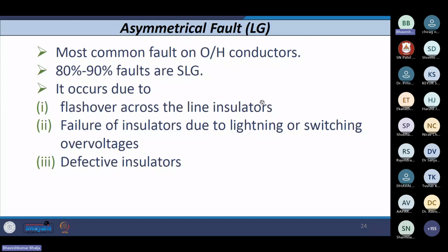Now, why do we bother about spacing between the conductors and the ground clearance? Because these two factors are important when we consider any type of fault. Usually 90 to 95% of faults are asymmetrical in nature, and 90% of those are single line to ground, so we are more concerned about single line to ground. This fault occurs because of flashover across the insulators, or failure of insulators due to lightning or switching surges, or defective insulators, which are very rare.